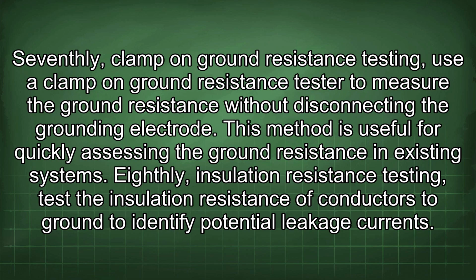Seventhly, clamp-on ground resistance testing. Use a clamp-on ground resistance tester to measure the ground resistance without disconnecting the grounding electrode. This method is useful for quickly assessing the ground resistance in existing systems.